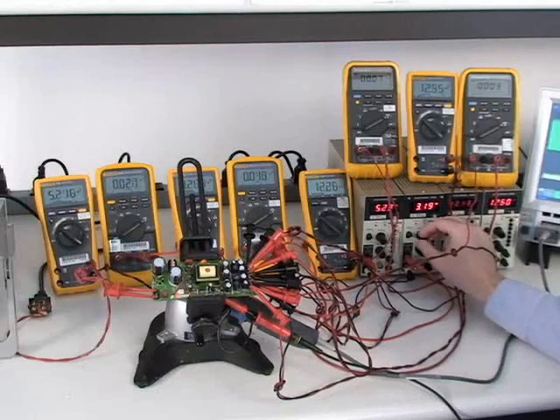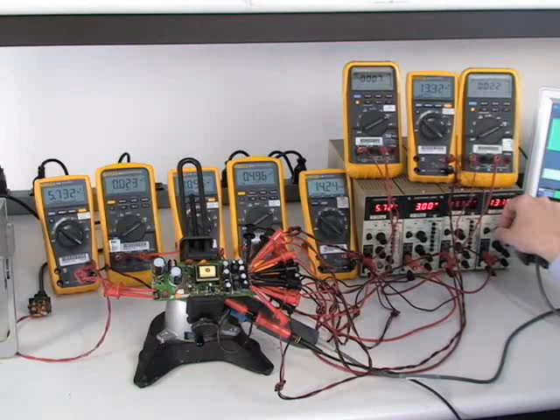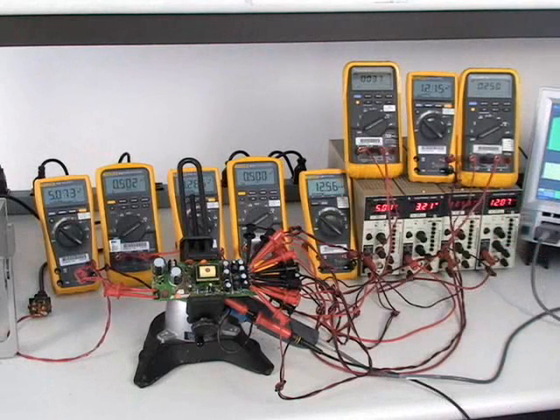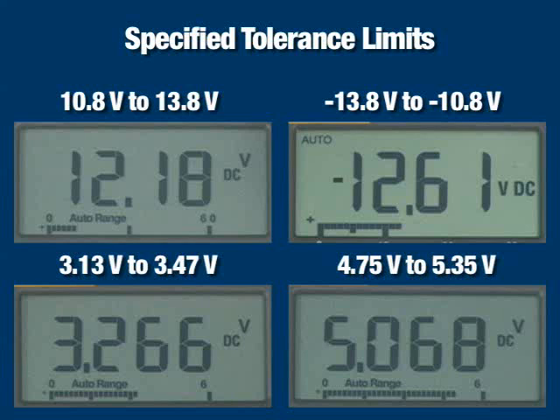Beginning with the primary output, slowly increase the loading on each output, one at a time, up to the full rated load for that output. Continue until all outputs of the power supply are providing full specified output power. Your power supply is now operating at the maximum continuous output power. All outputs should be stable and within the specified tolerance limits. If they're not, then stop testing and see the PI University troubleshooting curriculum to debug the problem.